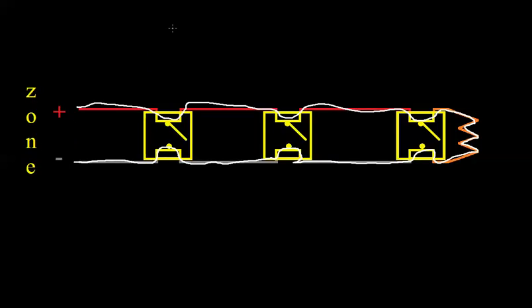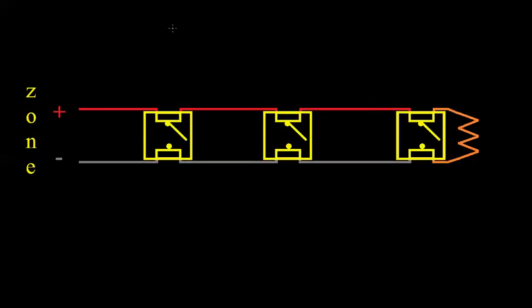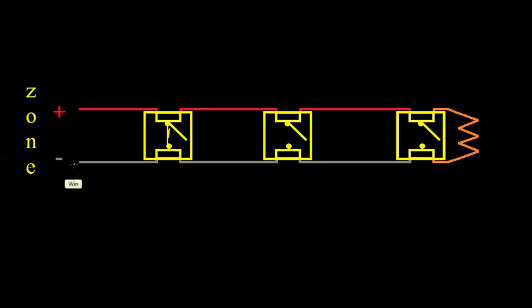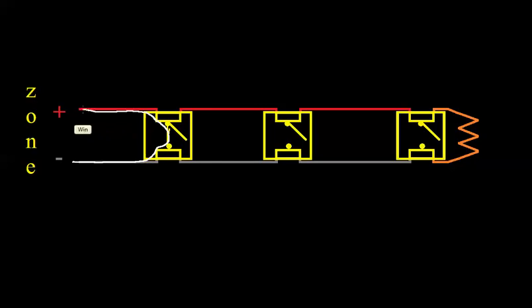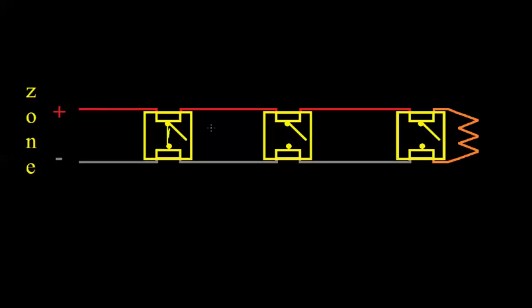If one of these were to go into alarm, let's say this is a pull station and it shorts out, somebody walks up and pulls it, and now the positive and negative are touching. The current's going to take the path of least resistance. So it's going to go right through that pull station. The current's going to increase, and the panel's going to detect that as an alarm. If somebody were to cut a wire, no current would flow, and it would detect that as a trouble.